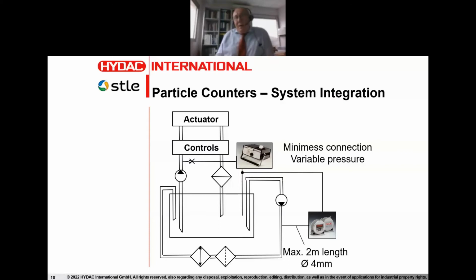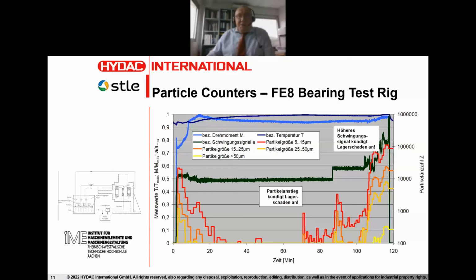So this is one way of making sure that the filter element is doing its job. Another thing to do is to put it on the return line so that you can actually see what is happening before the filter element, how the fluid is being returned to the system, or when it's being drawn out from the tank, what is being supplied to the filter elements and so on. So obviously in the ideal world, if the sensors were economical enough, one would have a distributed sensor array of particle counters, and through the system of checks and balances, one would be able to verify if the representation that one derives from the overall system picture is correct or not.